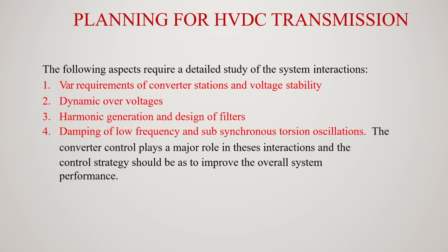The following aspects will require a detailed study of the system interactions. First is VAR requirement of converter stations and voltage stability. Second is dynamic overvoltages. Third is harmonic generation and design of filters. Fourth is damping of low frequency and subsynchronous torsional oscillations.